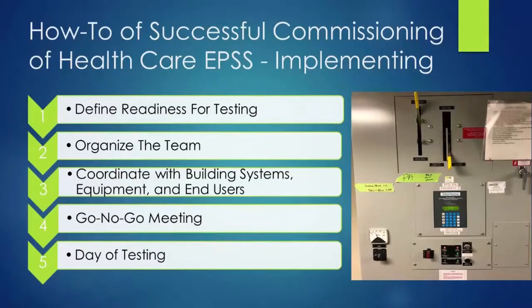That takes a long time. It's a complicated system to have the vendor come in and program. You want to make sure those checklists are taken care of before you set dates for testing. It's very important that all components are done.